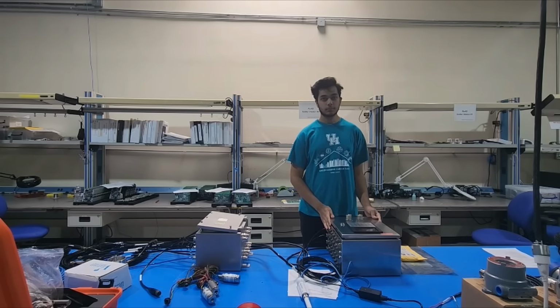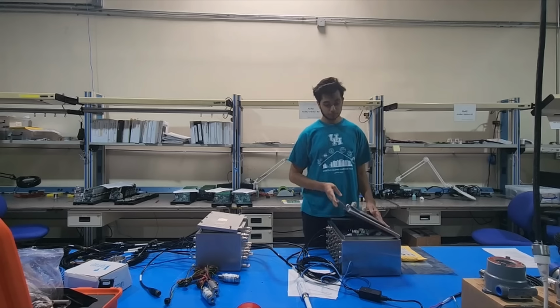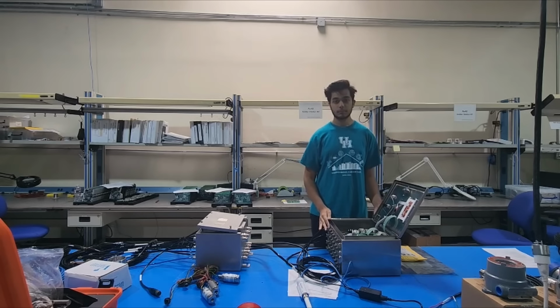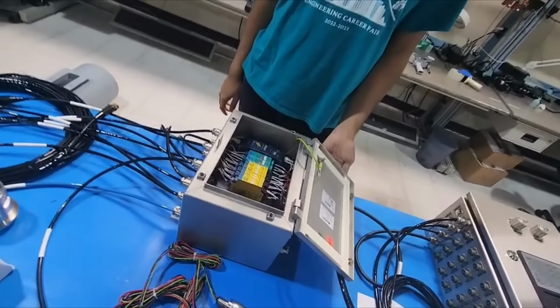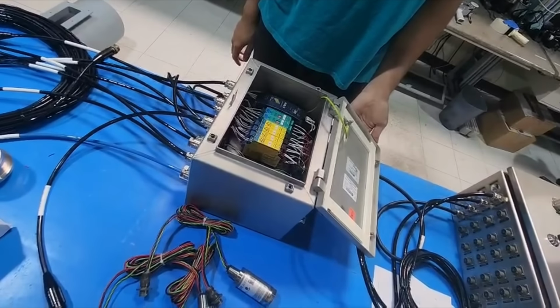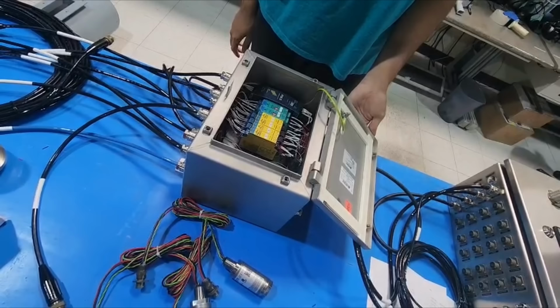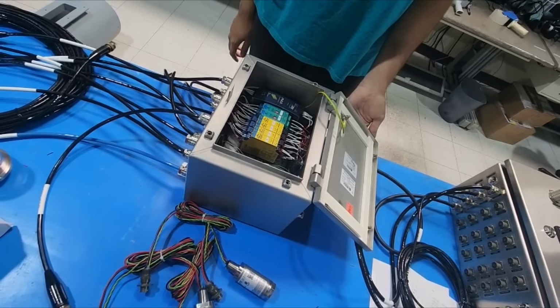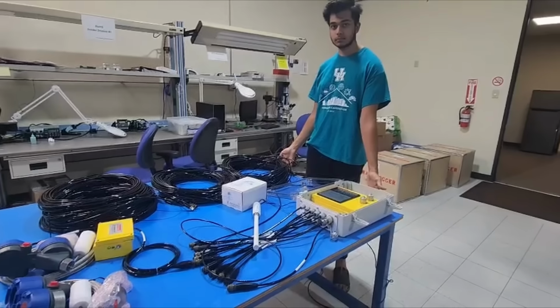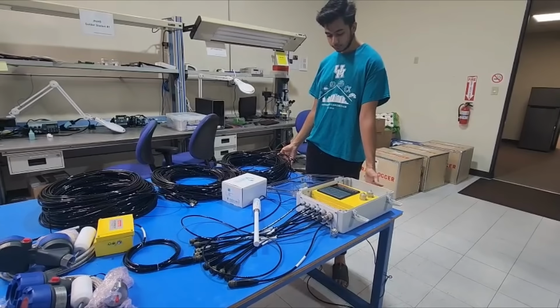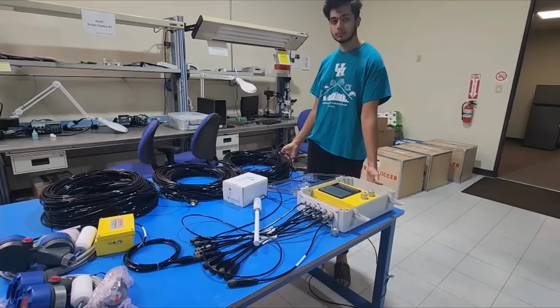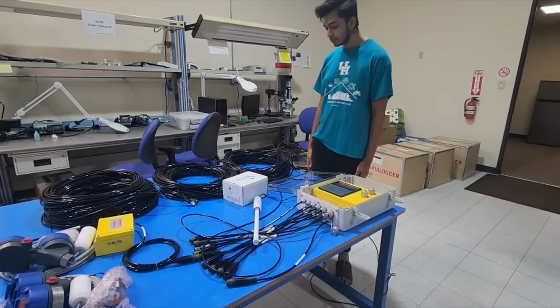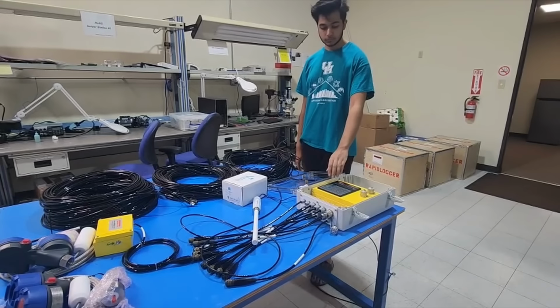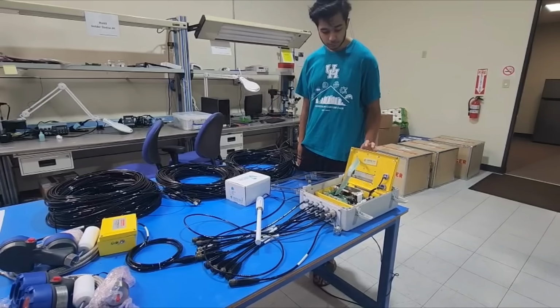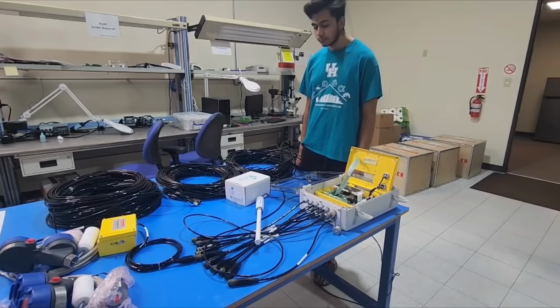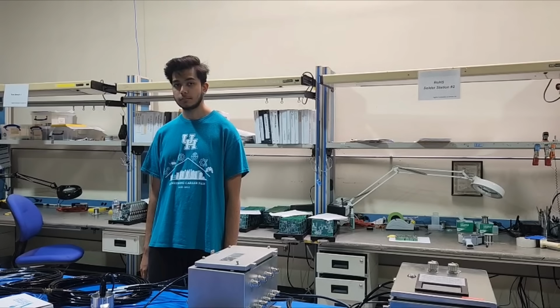This is the brains of the RapidLogger's data acquisition, and it is connected to the RapidLogger Zone 1 barrier box. The barrier box contains intrinsically safe barriers to allow signals from hazardous areas to be brought into the RapidLogger system without concern for sparking or arcing. The barge kit is meant for installation in a Zone 2 environment rather than a Zone 1 environment. Hence, it is certified as a non-arcing device, meaning that in the presence of explosive gases, this kit does not create a spark. However, an operator may not connect or disconnect any wires when hazardous gases are present.